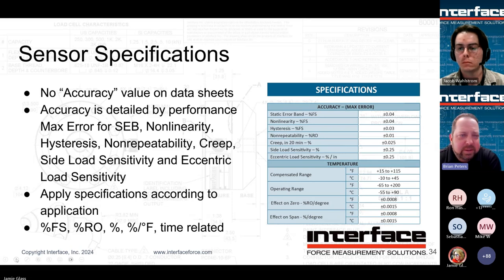accurate force measurements. Oftentimes customers ask us, what's the most accurate sensor you have? There isn't really a spec for that. It's going to come down to a lot of different parameters in terms of specific load cell performance aspects, but then also application details in terms of how you're using it, integrating it, what else you're hooking it up to, right?